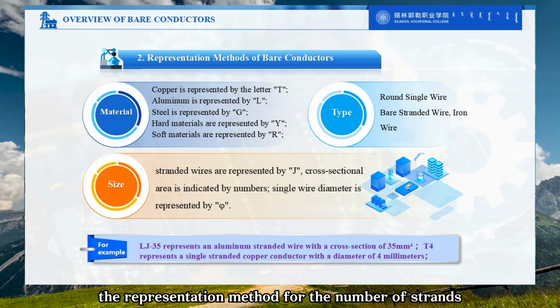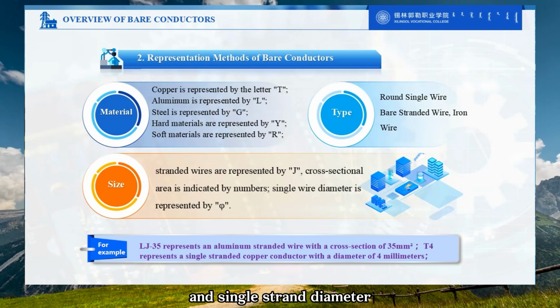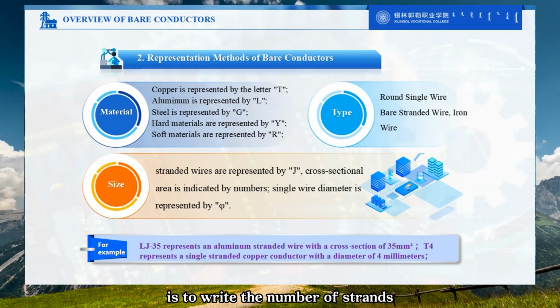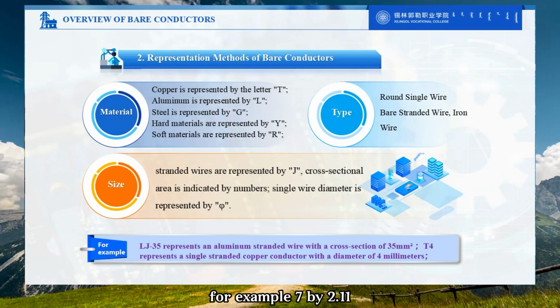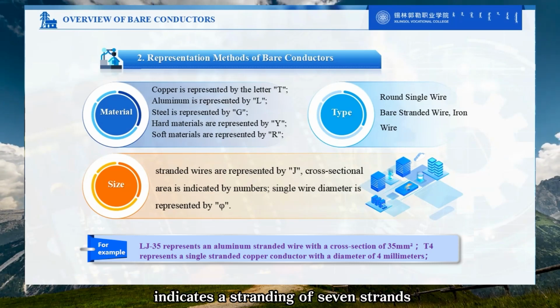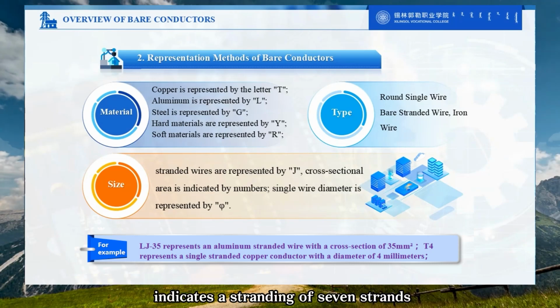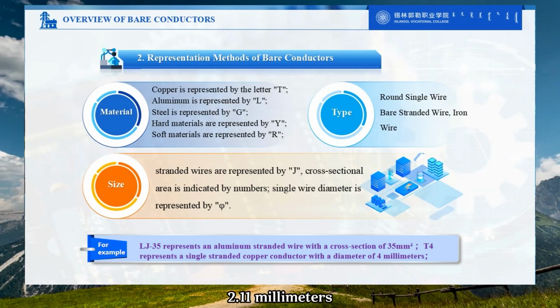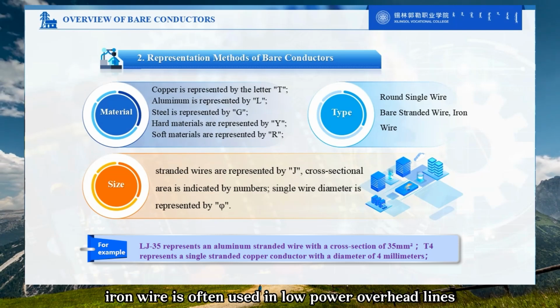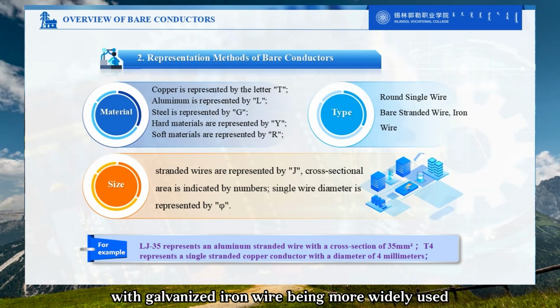The representation method for the number of strands and single strand diameter is to write the number of strands and the diameter together. For example, 7 by 2.11 indicates a stranding of 7 strands, each with a diameter of 2.11 millimeters. Iron wire is often used in low-power overhead lines, with galvanized iron wire being more widely used.